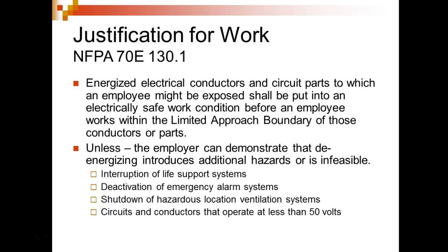And this has to be true unless the employer can demonstrate that de-energizing introduces additional hazard or is infeasible. For a hospital, it would be impossible, because if they kill the energy to the hospital, they'd kill people, right? In that situation, you could probably prove that people need to work on energized equipment. But in normal manufacturing, like Mercedes, there's no way shutting down a line and not putting out a car is worth justifying somebody getting killed by electrical shock.